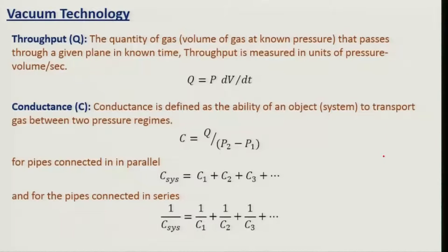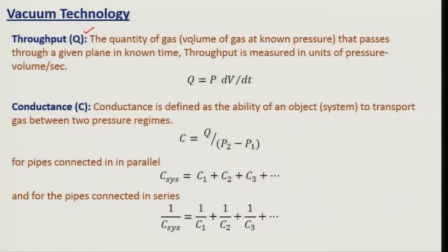Before we go and learn about different types of vacuum pumps and how to create vacuum, let me introduce some definitions. The first one is throughput, Q. Throughput is defined as a quantity of gas — the volume of gas at known pressure — that passes through a given plane in a known time. So if I am passing some gas through a plane in known time, how much gas has passed through is the quantity called throughput.